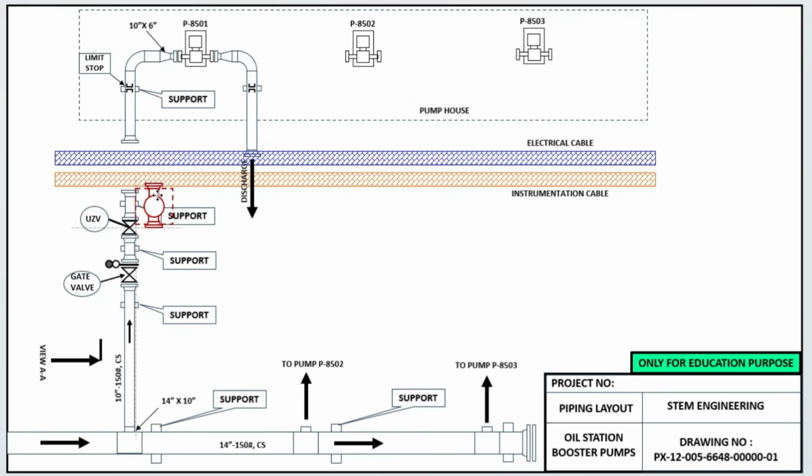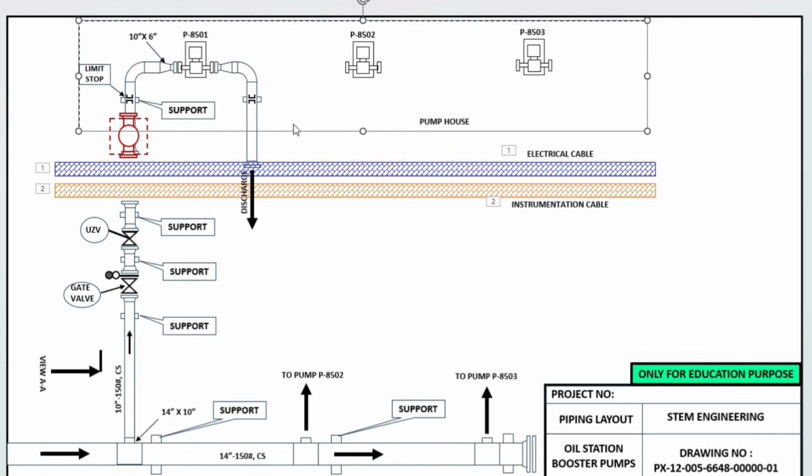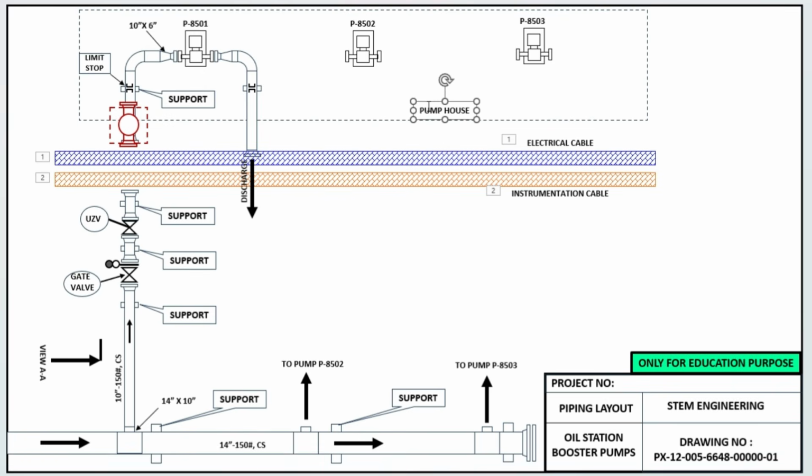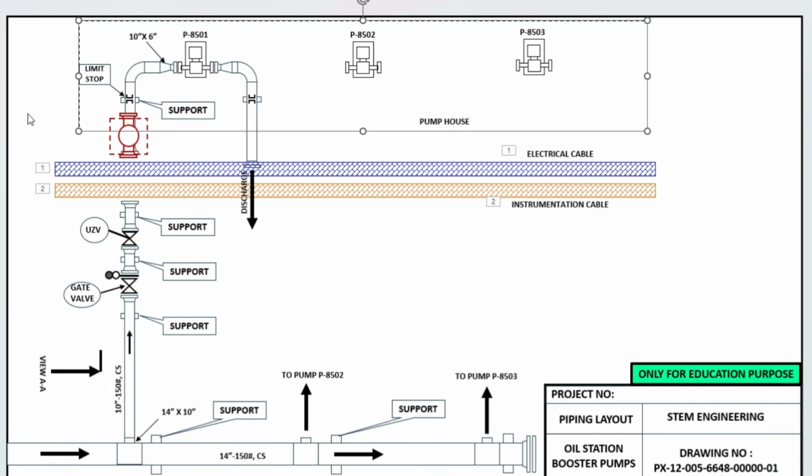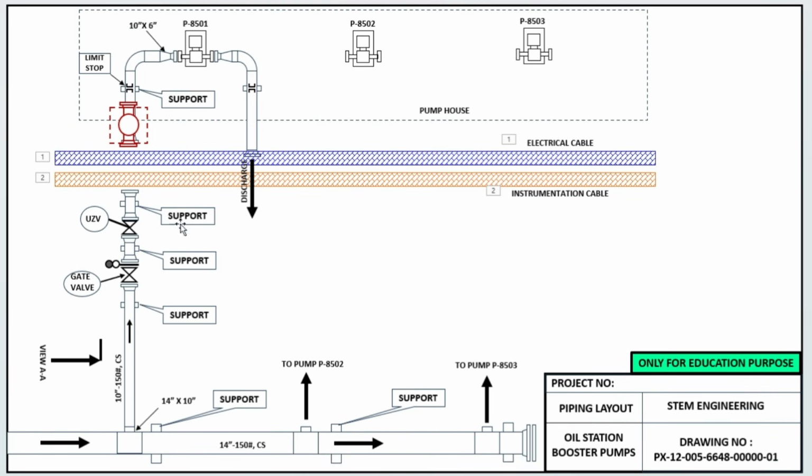So all I have to do is move the strainer here and there in order to see whether I can find a better location or not. So I could see a spool of piping over here. So I'm going to push the strainer a little bit in front in order to see whether I can place it or not. So I'm going to place it over here. But after placing it over here, I can see that it is exactly clashing with the pump shelter. Pump shelter is an area which has a paved concrete platform. So if you have to place a new basket strainer, you will have to demolish parts of the concrete platform, which is not recommended. So it is pretty much evident that I cannot place a basket strainer in the pump shelter.